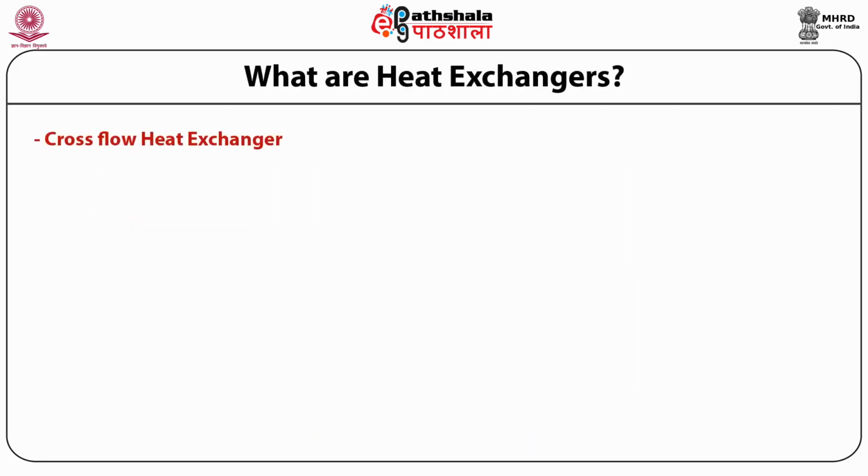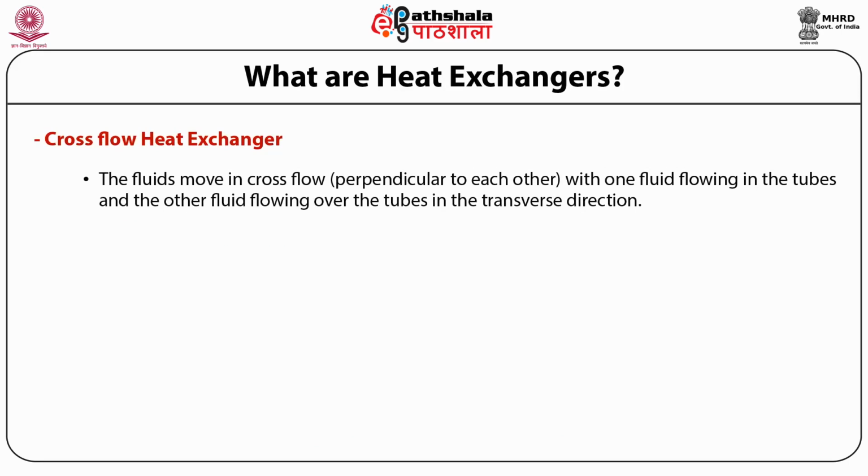Cross flow heat exchanger. The fluid moves in a cross flow. In the case of a cross flow heat exchanger, cross flow means both the fluids move perpendicular to each other. One fluid flows in the tube and the other fluid flows over the tubes in the transverse direction. So, if the hot fluid is moving in one direction, then the cold fluid will be moving perpendicular to the direction of the hot fluid.